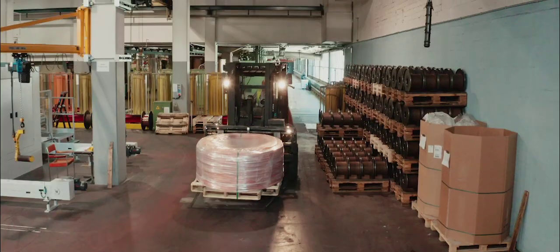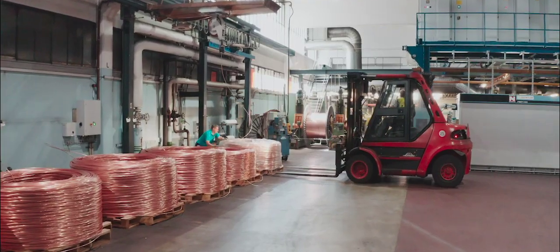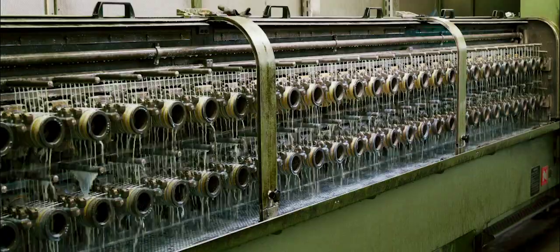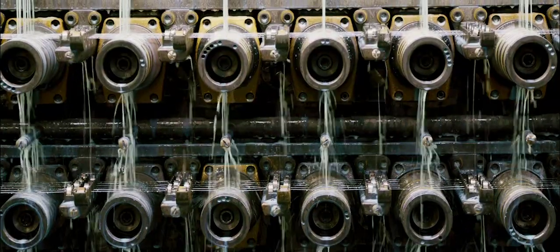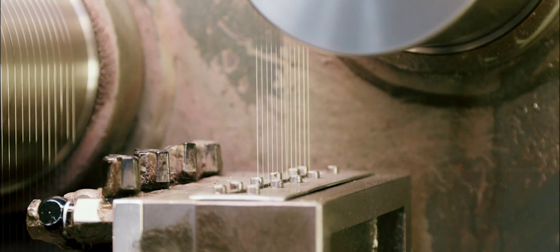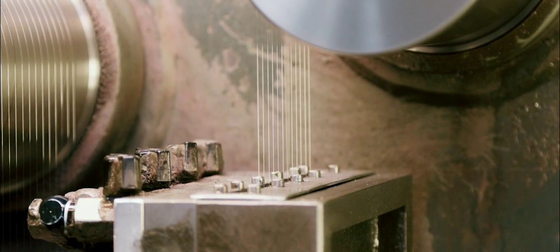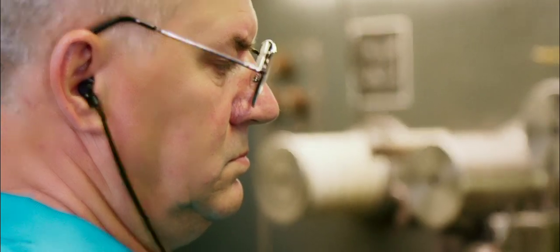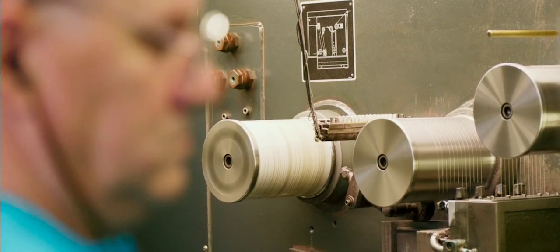For the production of our copper cables, 5,000 kg copper rings with a diameter of 8 mm are purchased. On various drawing plants, a final diameter of as little as 0.1 mm can be drawn. Stranding machines can produce flexible conductors with various numbers of wires, diameters, and lay ratios. This step of the process requires a flawless initial product in order not to affect the following processes.